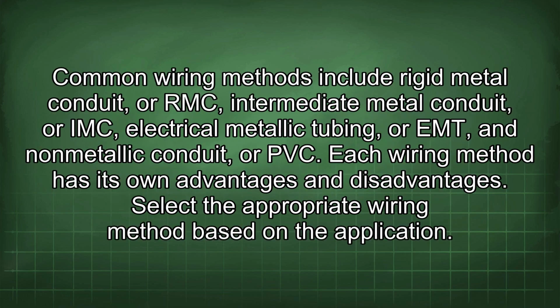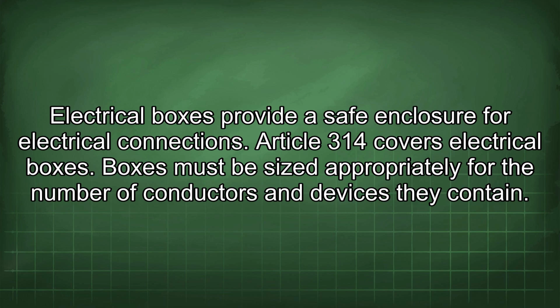Common wiring methods include rigid metal conduit, or RMC, intermediate metal conduit, or IMC, electrical metallic tubing, or EMT, and non-metallic conduit, or PVC. Each wiring method has its own advantages and disadvantages. Select the appropriate wiring method based on the application. Electrical boxes provide a safe enclosure for electrical connections. Article 314 covers electrical boxes. Boxes must be sized appropriately for the number of conductors and devices they contain.